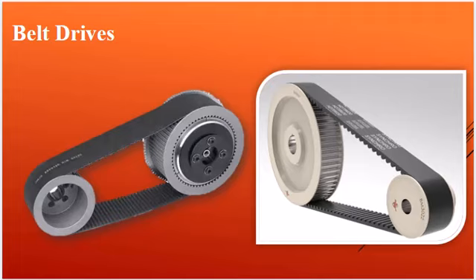Belt drives. Belt drives in fan systems are a mechanical method used to transfer power from the motor to the fan. They consist of a belt looped around pulleys, one connected to the motor and the other to the fan shaft, enabling the motor to drive the fan at the desired speed. Belt drives are popular in fan systems because they provide flexibility in speed adjustment by using pulleys of different sizes to achieve variable speed ratios without changing the motor's operating speed.